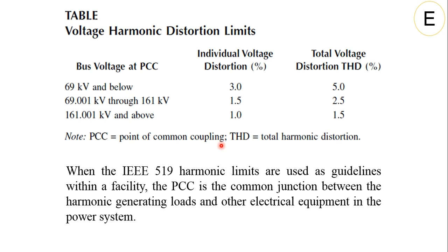So what are the voltage harmonic distortion limits at the bus voltage and the various ranges of the bus voltage? At the PCC, this much limit is what the standards are saying, and when IEEE 519/2014 is used as a guideline within the facility, the rules for grid harmonic injection are very strict. So people are accommodating harmonic current mitigation, and it is estimated that 70% of the loading of a facility will be due to nonlinear loads.